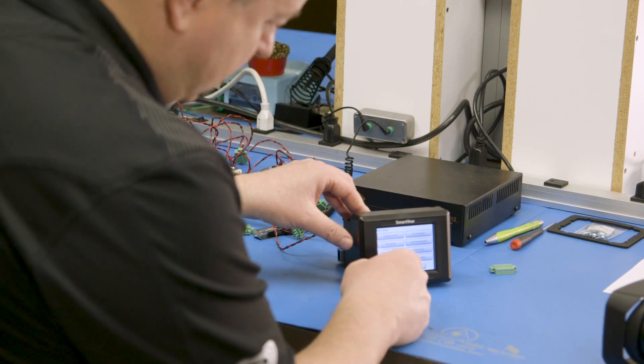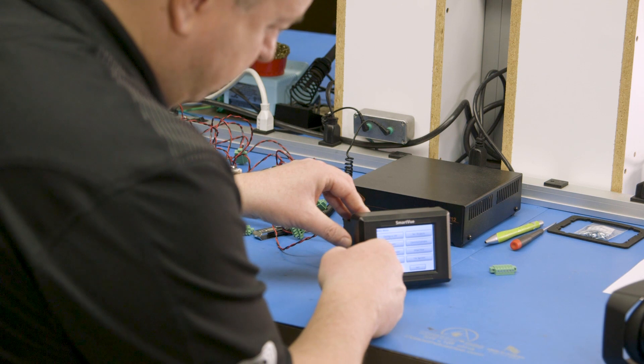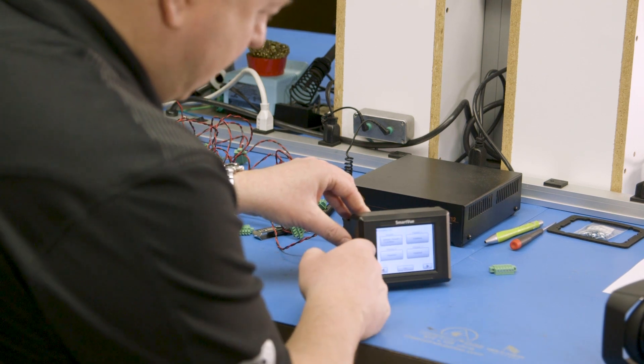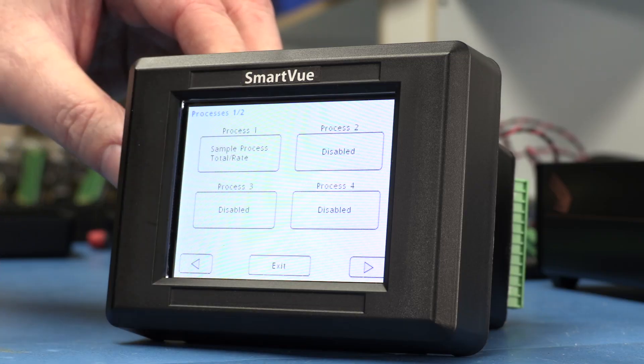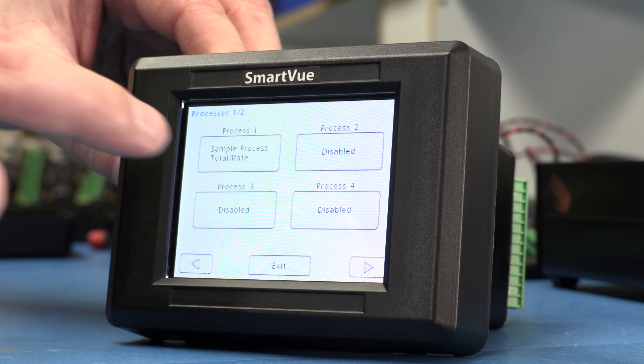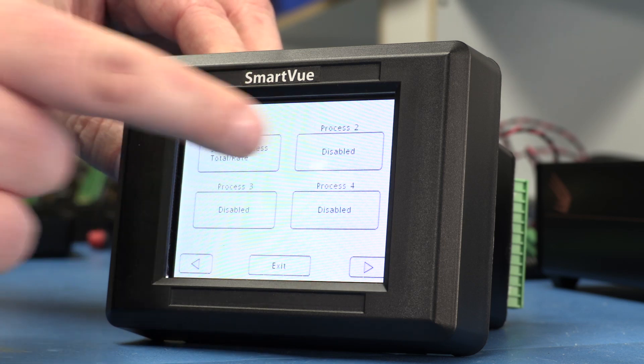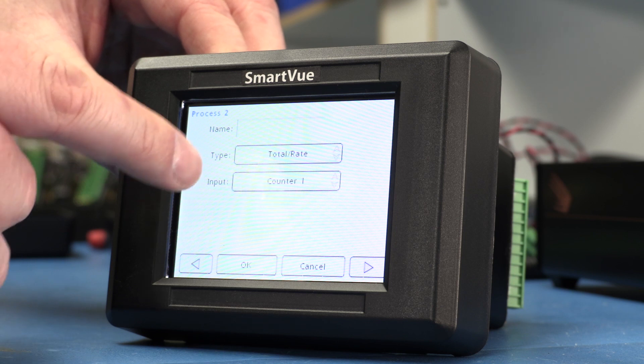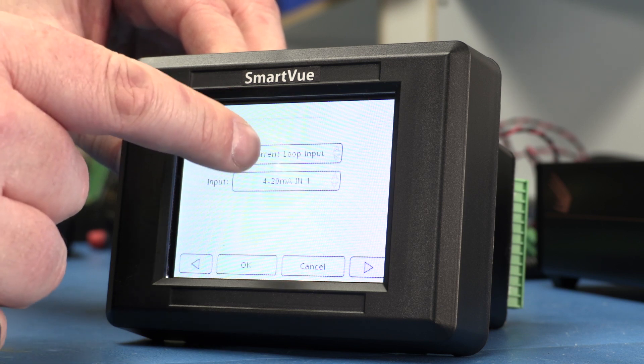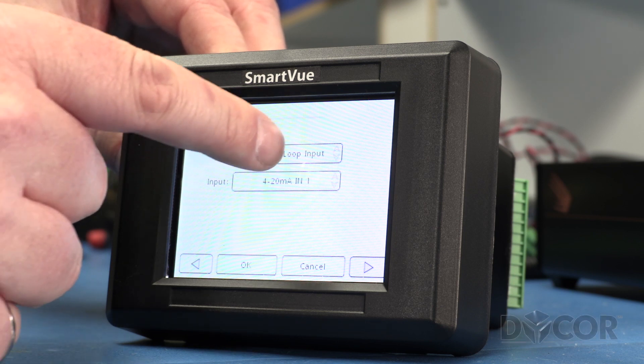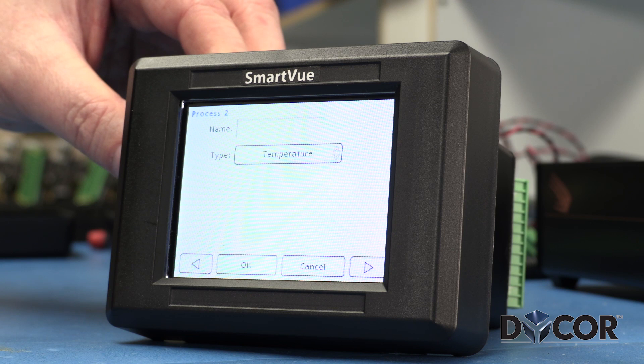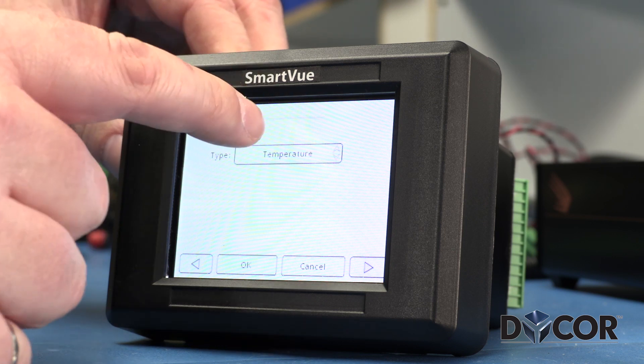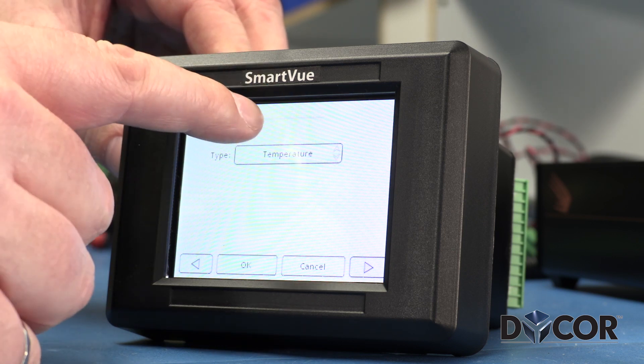I press the menu button, then the processes button. You can see the existing Process 1. I'm going to add Process 2 — it says disabled now, but I'm going to enable it and select the type of process, which is temperature. I'll type in a name for that process and simply call it Temp 1.